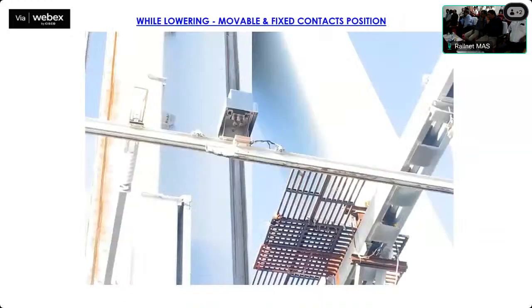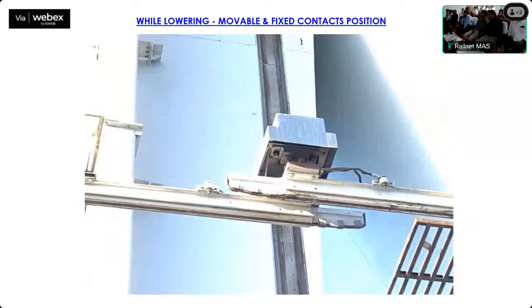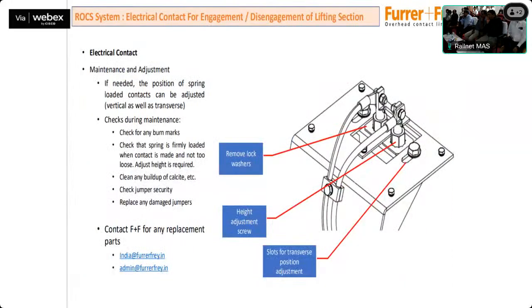Some of the suggested maintenance includes checking for any burn marks, checking the springs are firmly loaded and not in loose condition, cleaning any buildup like calcite if present, and ensuring the jumper is secured properly and intact, without any loose contact - like typical OHE maintenance only.